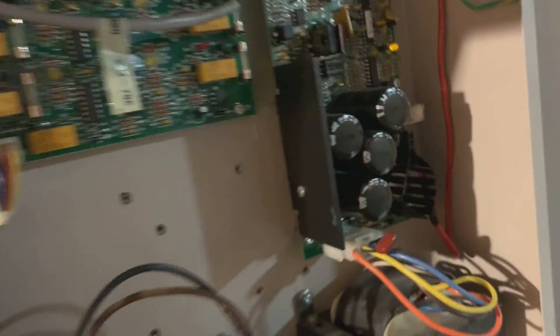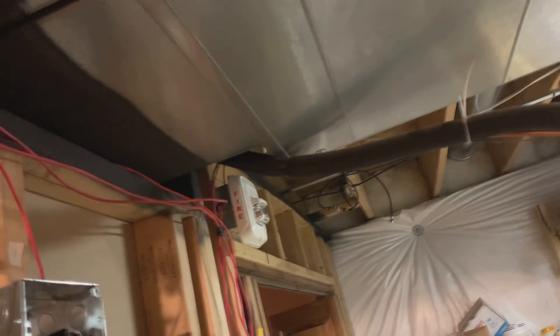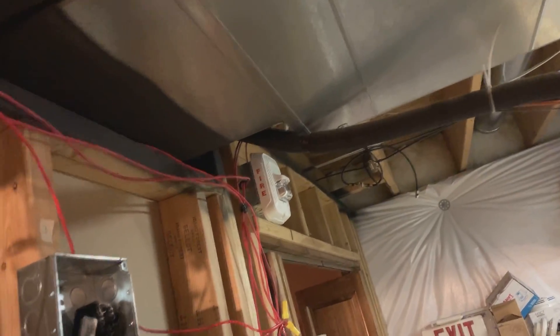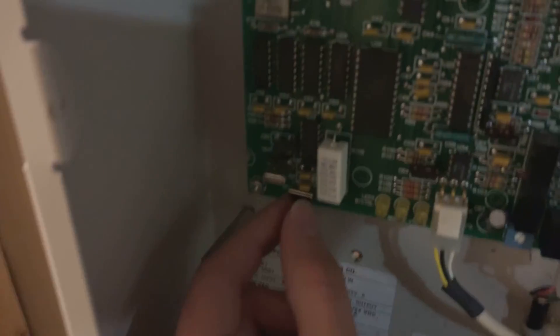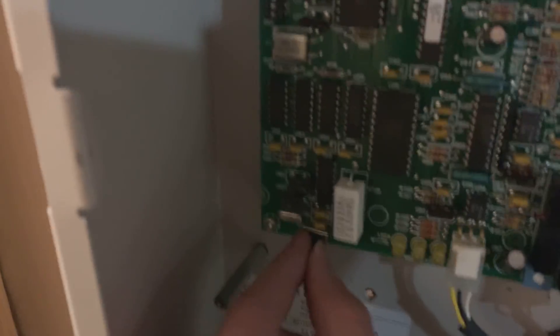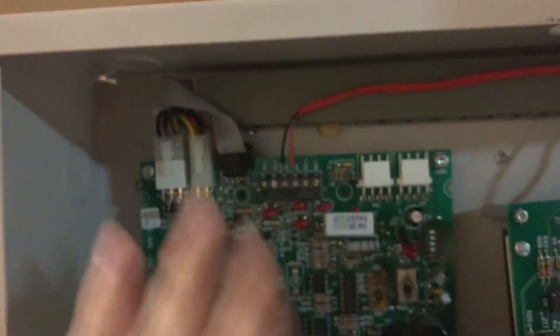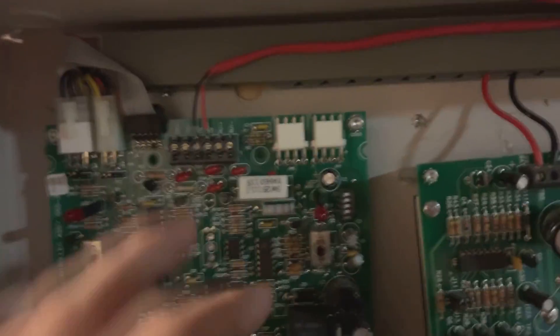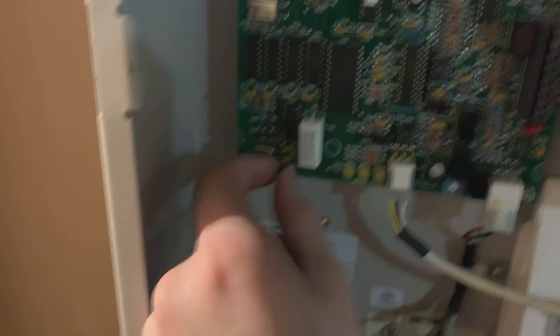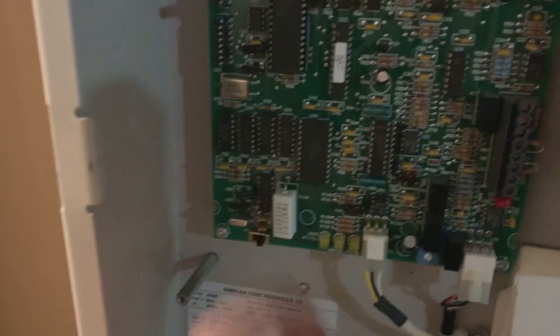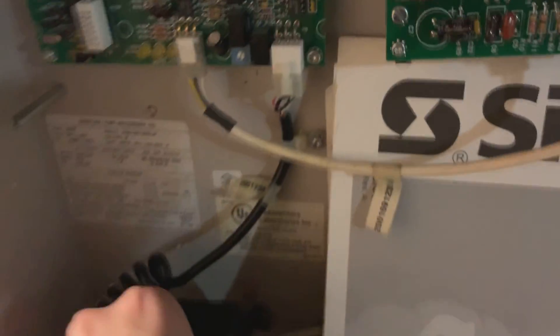If I have the positive wire there, it actually causes this thing to do a continuous horn sound that's awful. So don't do that. Over here, this switch here is a test switch. If I hit that, it silences this. So this thing now doesn't respond here. It causes a trouble on the 4010 because that part is supervised. So there's that.